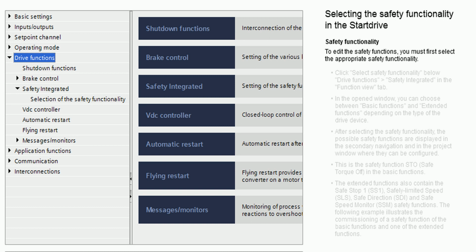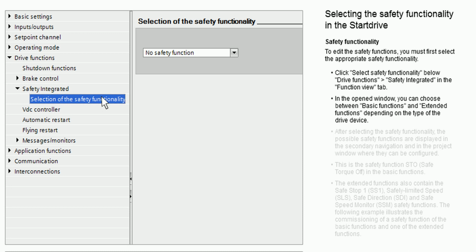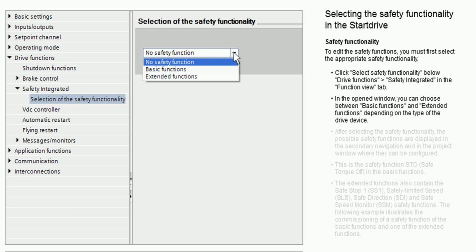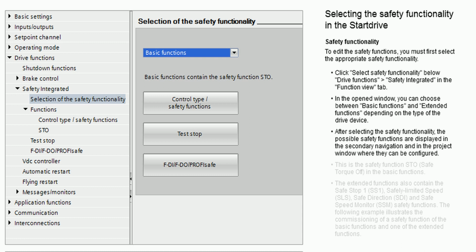Safety functionality. To edit the safety functions, you must first select the appropriate safety functionality. Click Select Safety Functionality below Drive Functions, Safety Integrated, in the Function View tab. In the opened window, you can choose between Basic Functions and Extended Functions, depending on the type of the drive device. After selecting the safety functionality, the possible safety functions are displayed in the secondary navigation and in the project window where they can be configured.